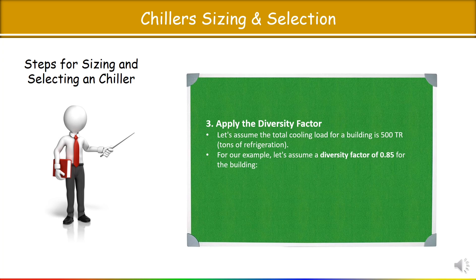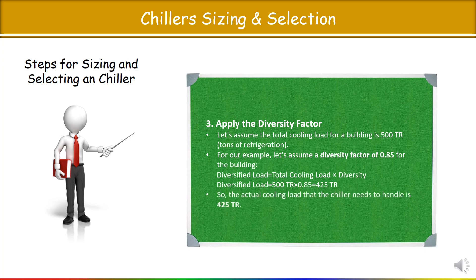With a diversity factor of 0.85, when you apply the formula, you get 425 TR. In this way we can save cost on equipment and energy consumption. You have to do the sizing of the chiller as per this diversified cooling load. The actual cooling load that the chiller needs to handle is 425 TR — remember this point.